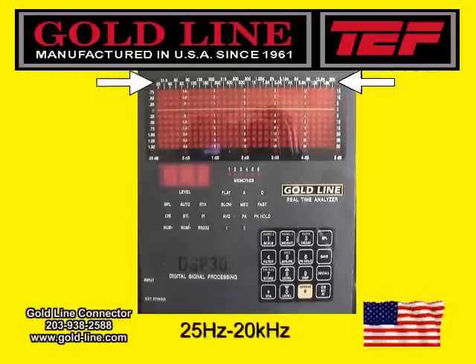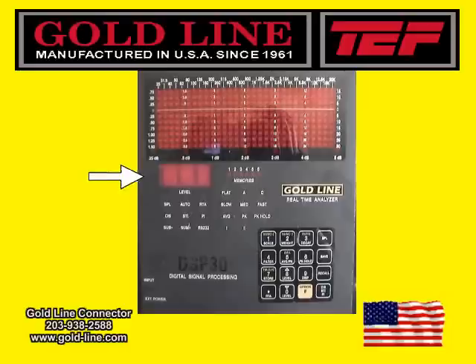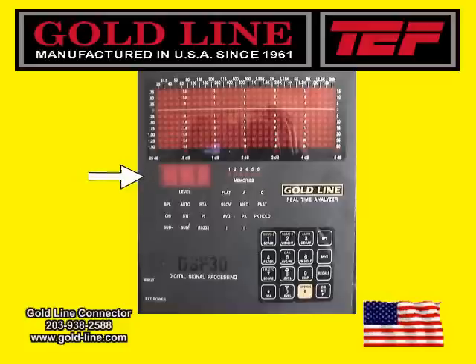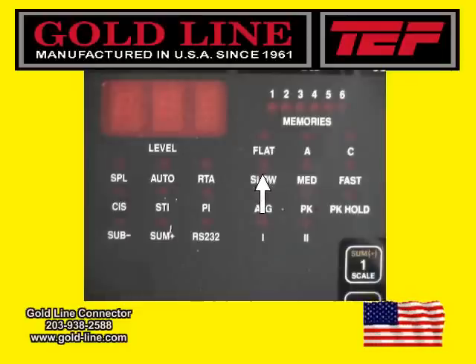The top of the display shows you the 1 third octave ISO center frequencies. The frequencies range from 25 Hz to 20,000 Hz. The smaller LED screen below the main screen displays an accurate sound pressure level. SPL can be read as a reference level or an accurate broadband measurement. Depending on the test requirements, you can measure and display the SPL in flat, A, or C weighting.